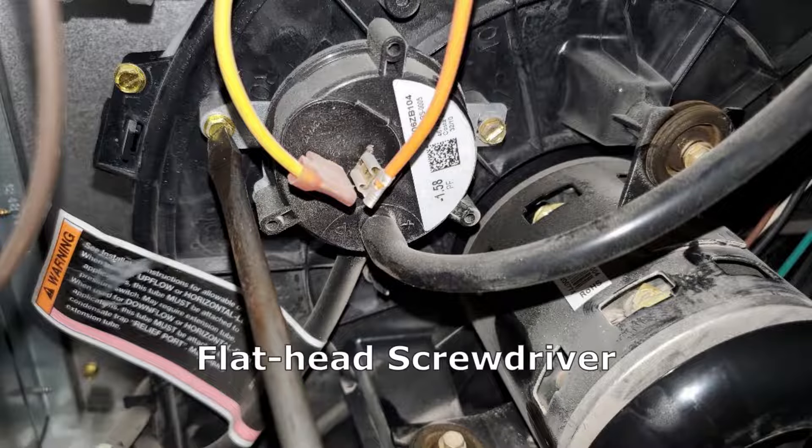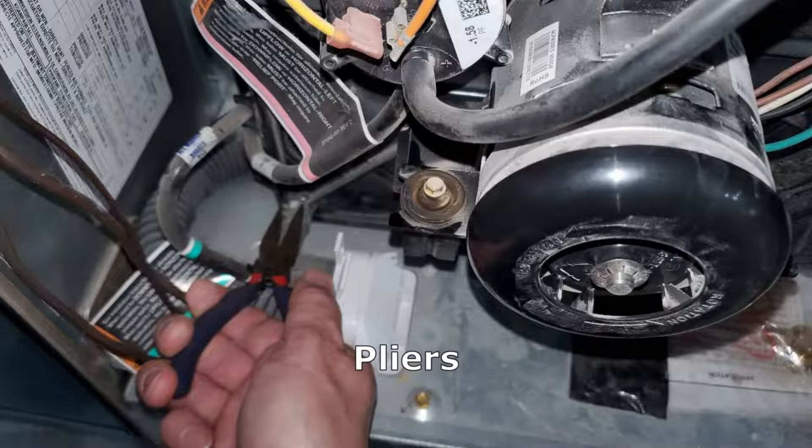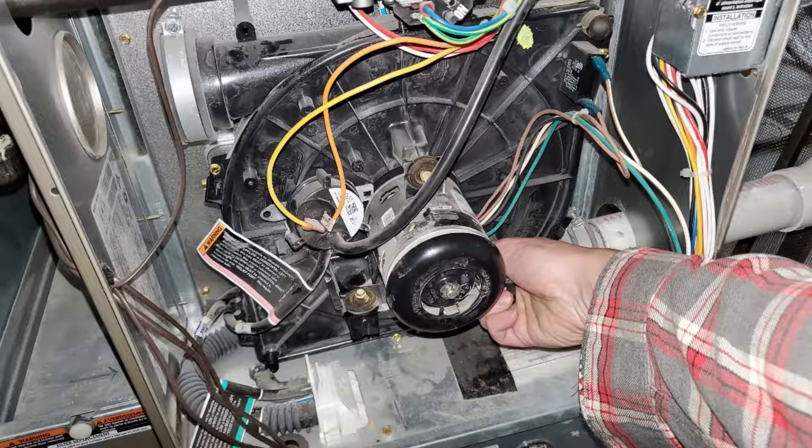There's a pressure switch on the unit — we'll be reusing this — so remove that using a flathead screwdriver with two screws, and then remove the small pipe clamp from the drain hose near the bottom. At that point the draft inducer motor should pull straight outward.